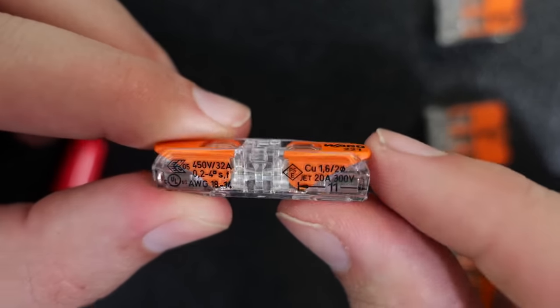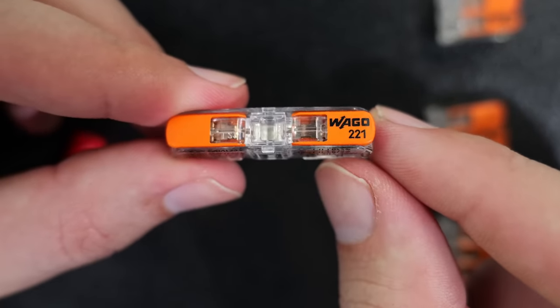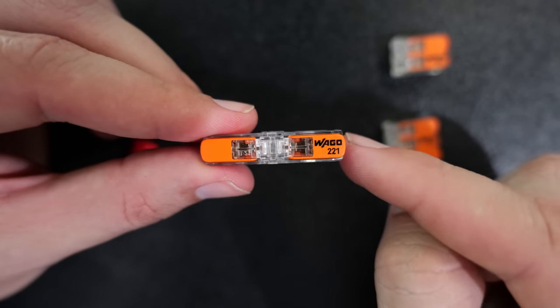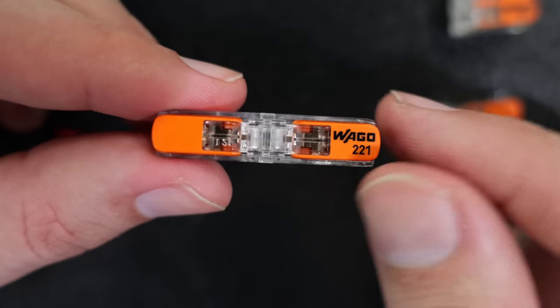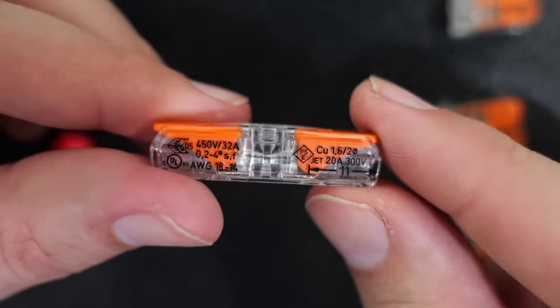The inline connector, while it is quite a bit larger in diameter than a regular wire, it still is fairly close and resembling a wire. So I really like these, especially in light switch boxes. Again, usually a very low amperage situation. And I'm okay with using these to connect 15 amp receptacles. Again, it says it's rated for 20 amps, so we're well below that 20 amp rating. And for the most part, most of the things that we plug into a 15 amp receptacle really don't usually ever reach that 15 amp capacity.